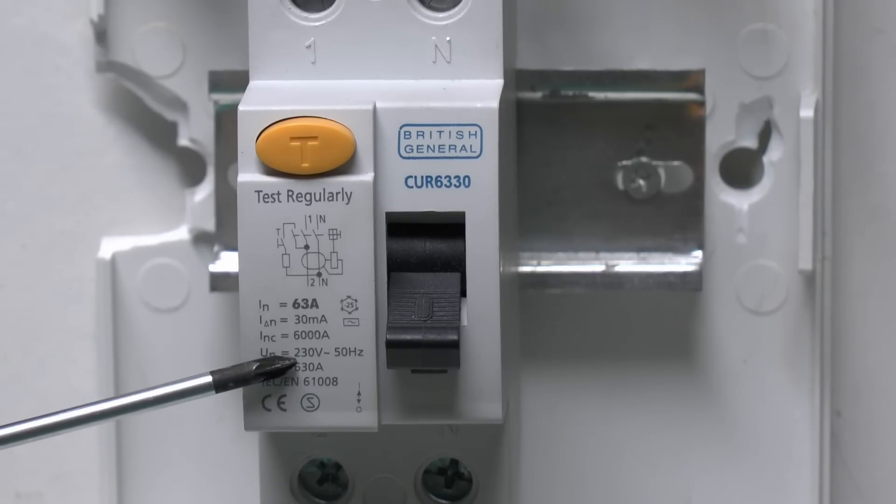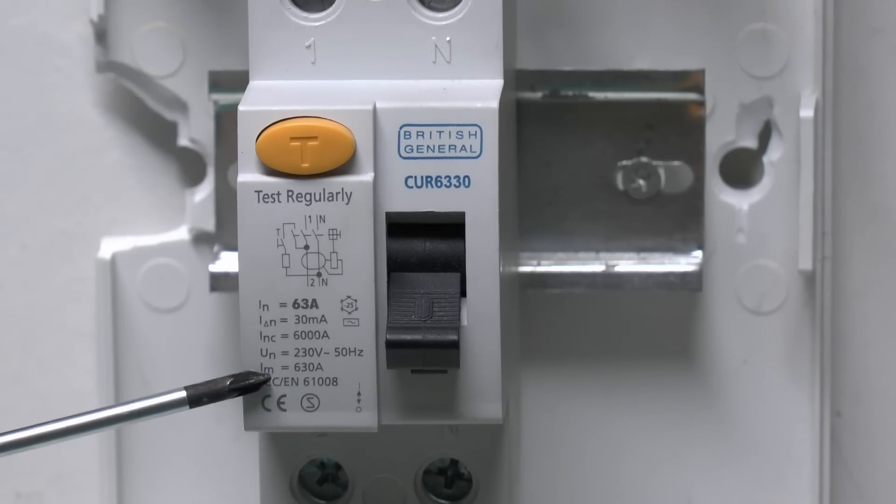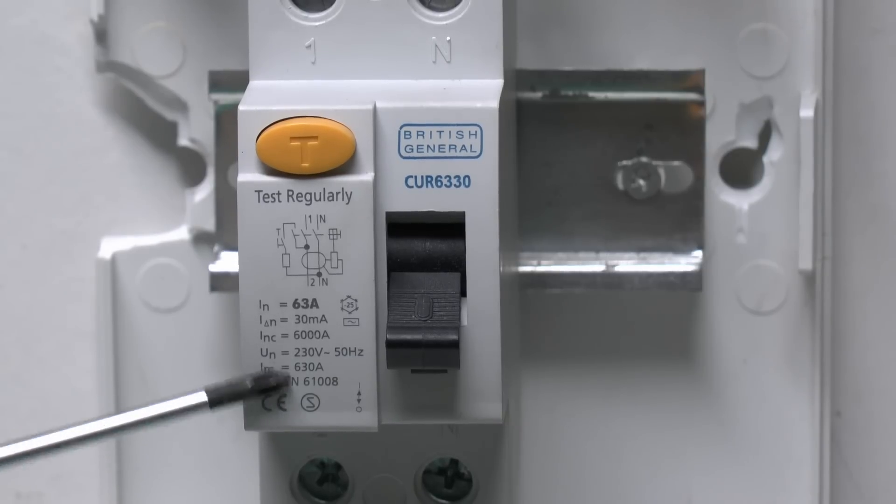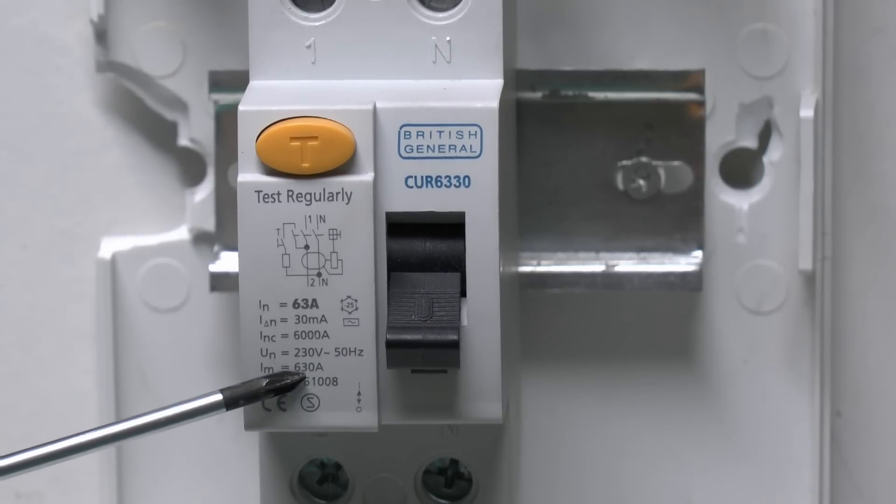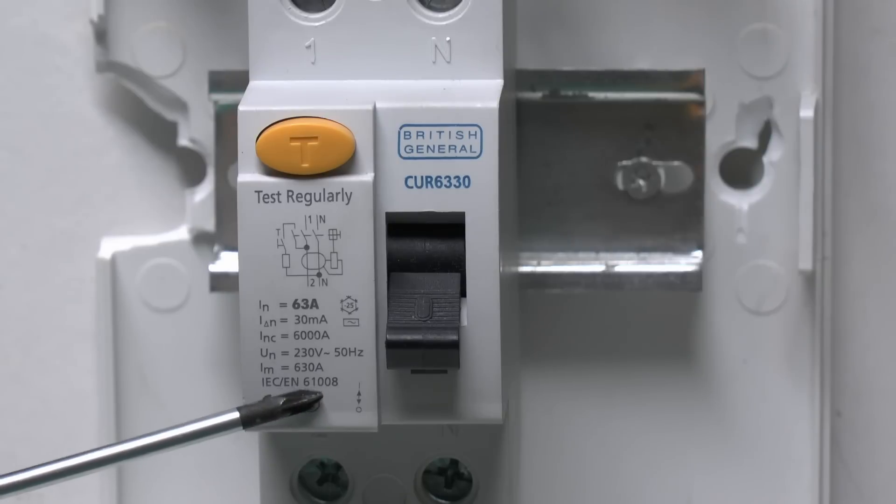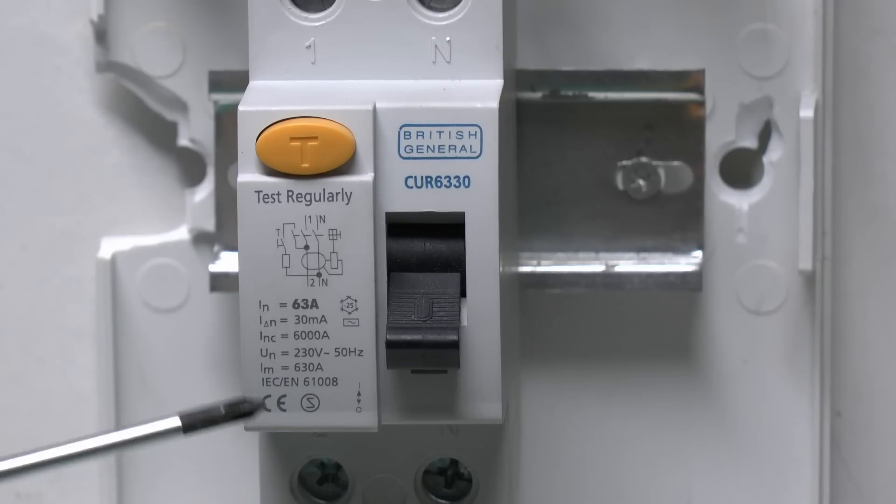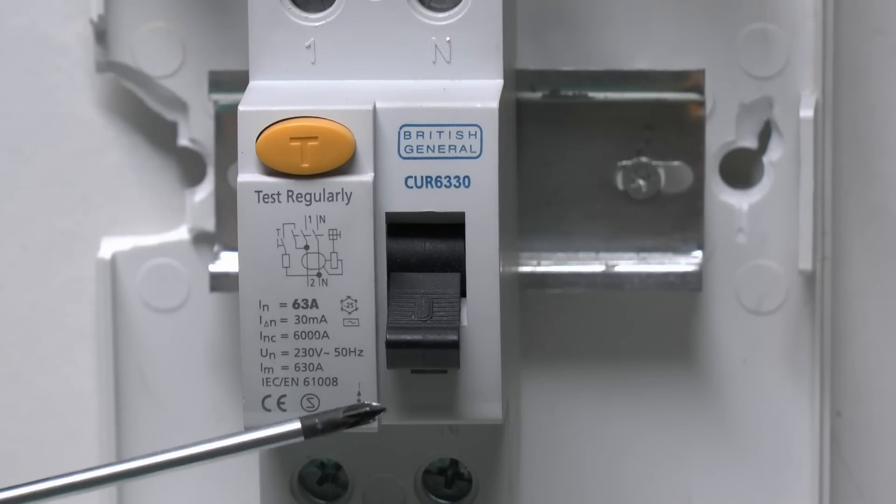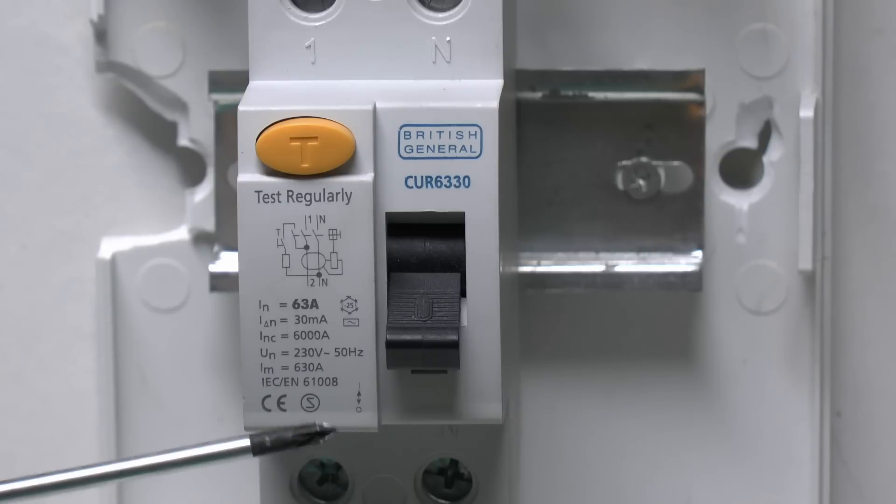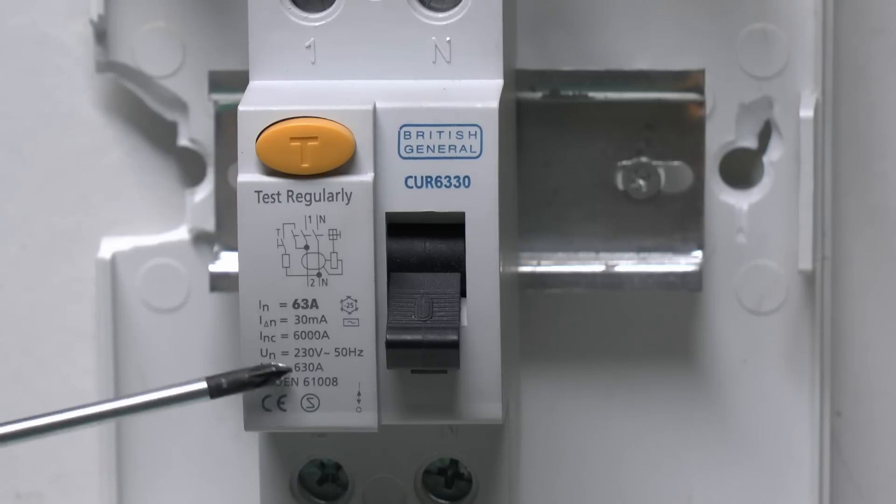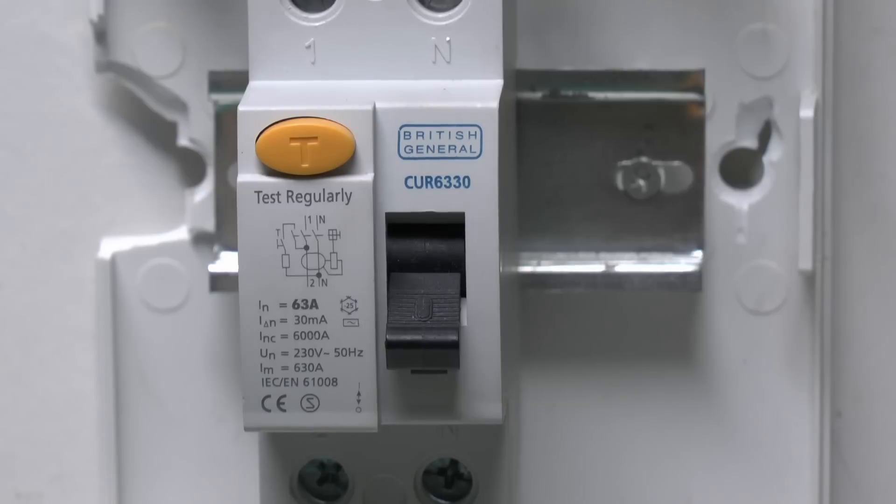The rated voltage there of course 230 and 50 hertz, and the making capacity, in this case 630 amps. Essentially that's the situation if there was a fault existing between say line and earth or line and neutral, and when it was switched on, that's the maximum amount of current that can flow without actually destroying the device.